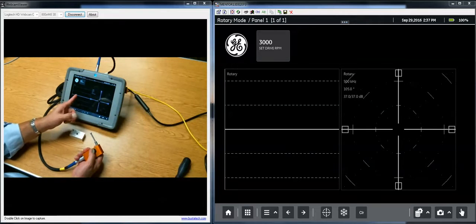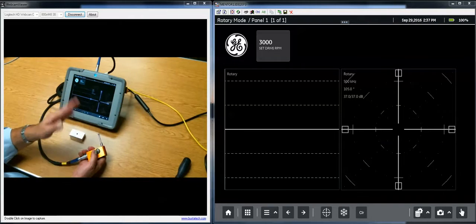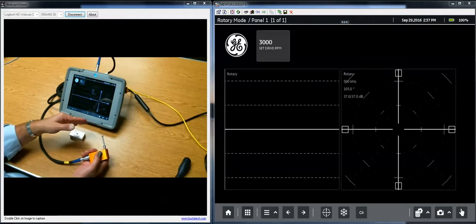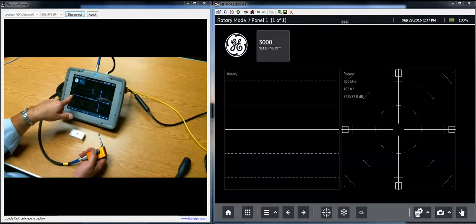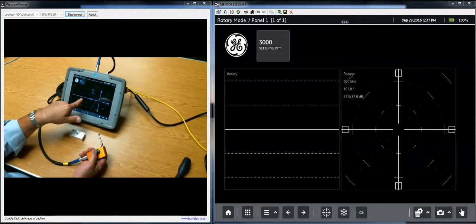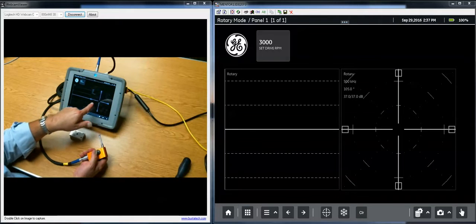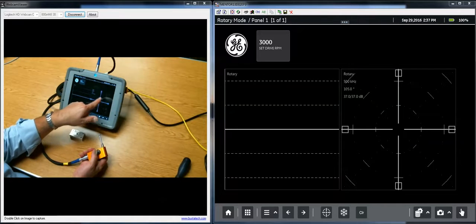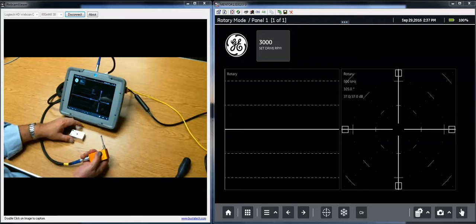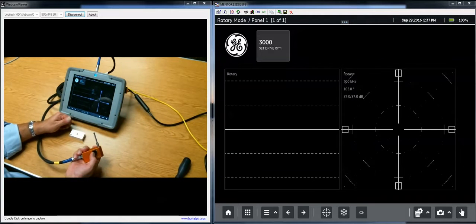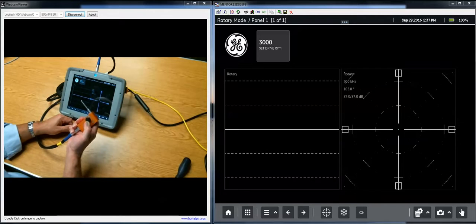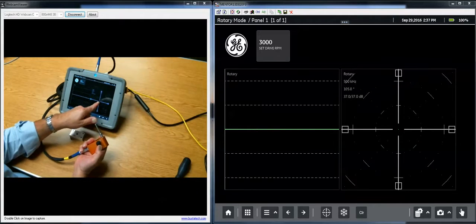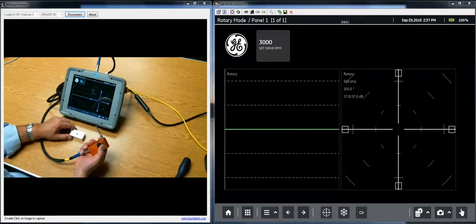So you're always looking at exactly one rotation, or again, you can select 2, 3, 4, 5 rotations, but you'll see one or a couple of rotations on the time view, and the same one rotation or so on the lissajous. And right now we have no data flowing because the probe isn't spinning. If I push the black button on the probe, it begins to spin. You see I have data now appearing. I've got a green dot in the center of the display. I've got a flat line on the time-based view in green.